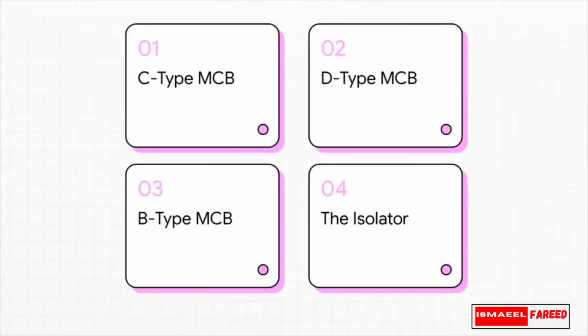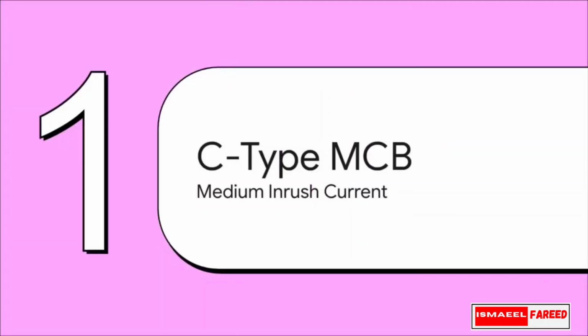So here is our roadmap for this explainer. We're covering the C-type for medium inrush current, the D-type for high starting current, the B-type for low inrush current, and finally, the isolator exception. The main thing we're tracking across all of these is inrush current. Basically, that initial surge of power a device pulls the exact millisecond you turn it on. All right, Section 1. The C-type, medium inrush current.